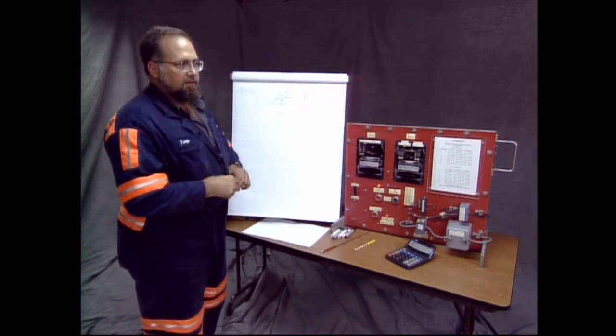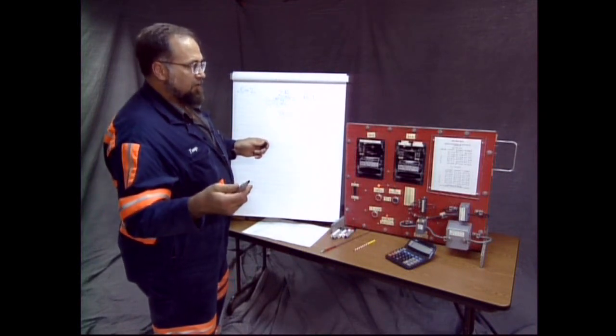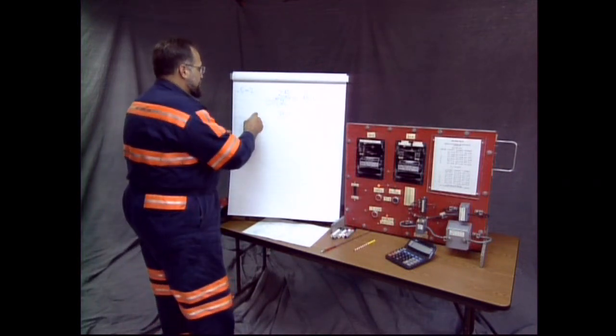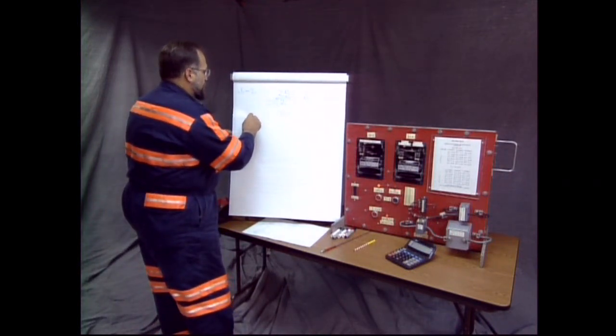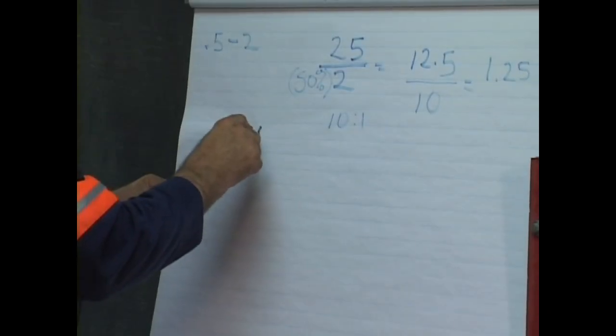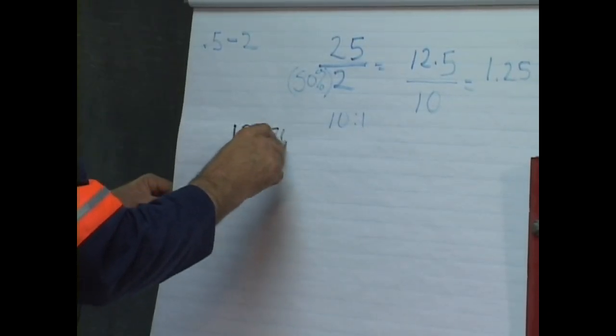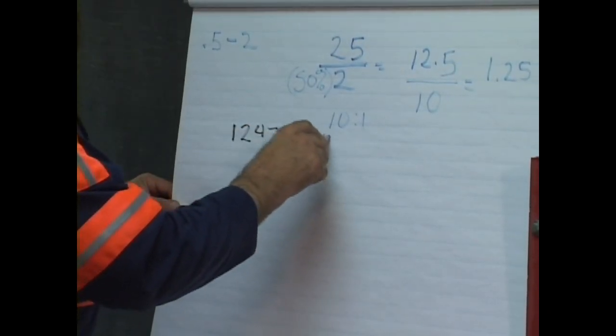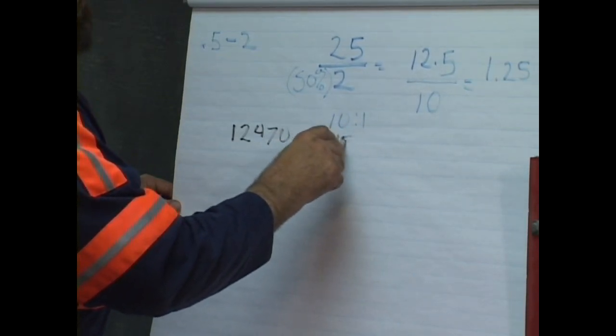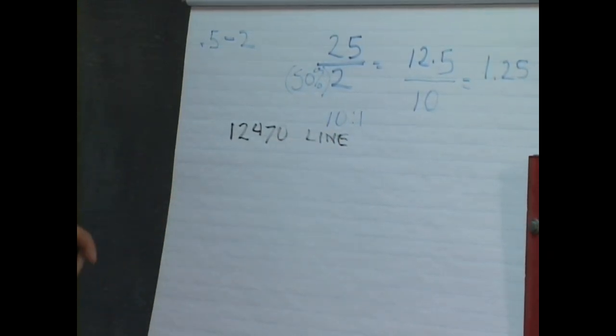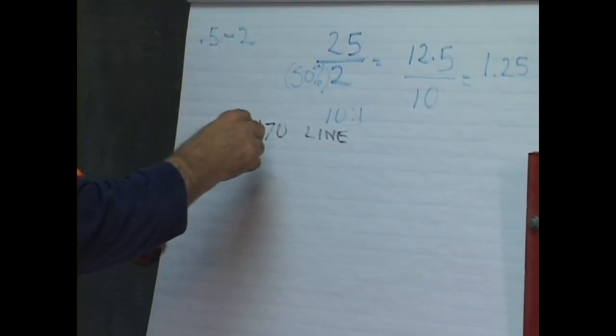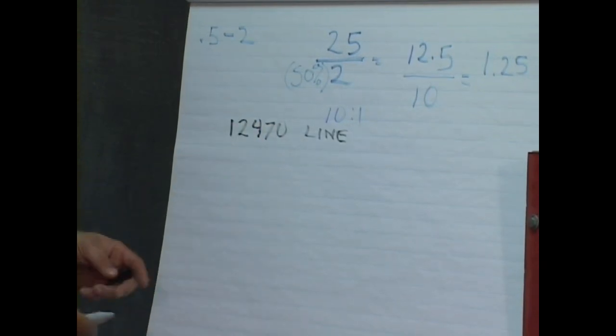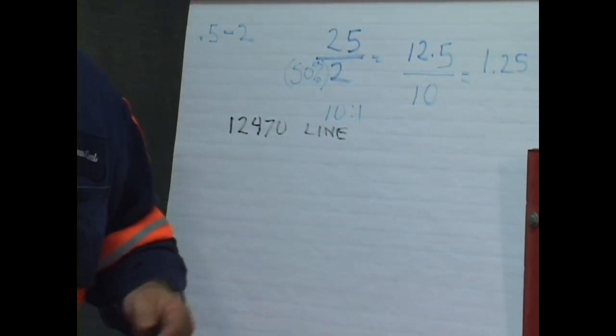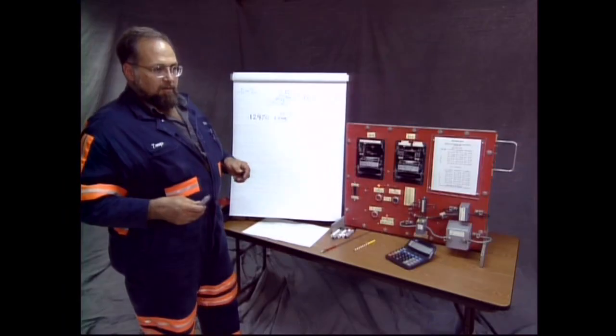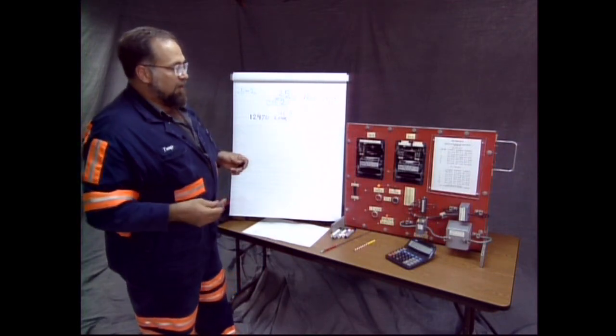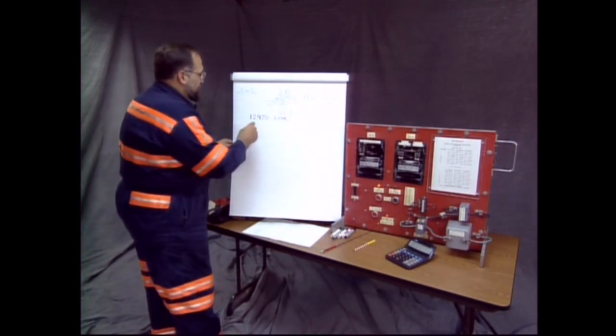Let's say that we have a system of 12,470 on our line. Okay, our line voltage, that's three-phase power, and we have a phase-to-phase reading of 12,470. Now we're going to apply the square root of 3 to that 12,470.